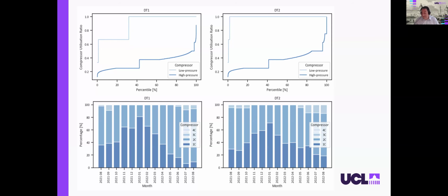So to have a reliable system running throughout the whole year, the system has to be properly sized. In those particular stores, they have 4 compressors to meet the demand throughout the year, so that on the warmest day there's no break in operation and the stock of food doesn't go wrong. But that means in the wintertime, most of those compressors are switched off - there's no need for them.